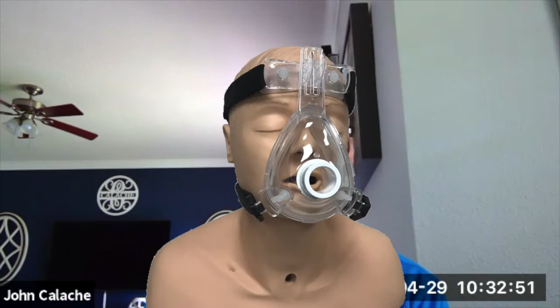It's very important with CPAP to maintain a good mask seal because we're giving them continuous PEEP, right? We're putting pressure in. You have to make sure that the mask that you're using is a non-vented mask. If your mask has a vent on it, all that PEEP is just going to come right out of the mask and it will not be able to maintain mask seal.